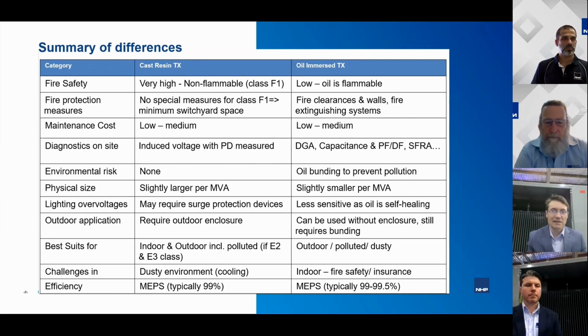Diagnostics on site: you can diagnose a cast resin transformer, though it's quite expensive, with methods where you can measure partial discharge on site. With oil transformers, there are more methods, more readily available, especially if you check the oil quality, where we compare oil to human blood. From a simple blood test, the doctor can tell lots of things about our body, and the same goes for the oil in the transformer. Environmental risk: certainly a benefit with cast resin is that it doesn't present any environmental risk, while the oil transformer always has a risk of oil leaking, and therefore special measures have to be taken, such as oil bunding. Physically, cast resin transformers are slightly larger per MVA versus the oil transformer.